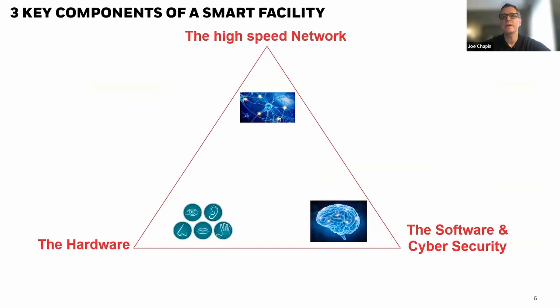So there are three different components of a smart facility. At the very top, you'll see a network. When I'm talking about networks, I'm talking about a high-speed network, whether it's your T1L at 10 megabit, your IP-based controllers, or wireless. The days of connecting to BACnet where your standard typical speed is around 76.8 kilobits, you can still connect to those, but with the availability of fast networks, you want to get to the high-speed network because of all the advantages. Number two, you've got to have the hardware.